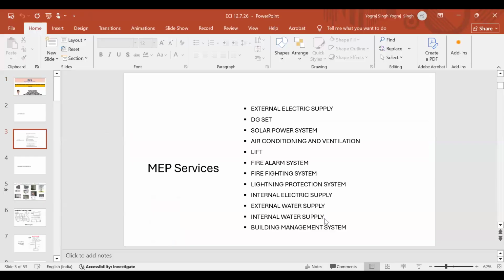First, whether it's a township, a multi-storied building or anything, we get supply from the state electricity board system. You can see on the right, there is an HT supply coming. That supply will first come into the HT metering kiosk. So metering is the first thing. Before that, there is only a cut point in the form of GOD or load break switch. One important thing I want to tell: a load break switch should not be confused with a VCB or circuit breaker. A load break switch is only to switch the normal load currents. It does not have short circuit handling capacity.